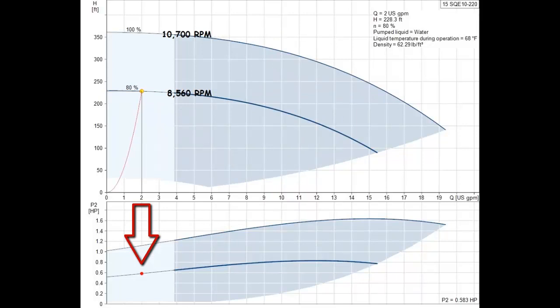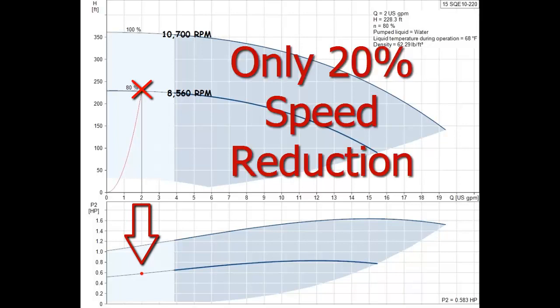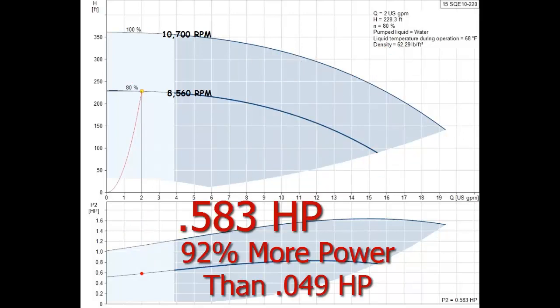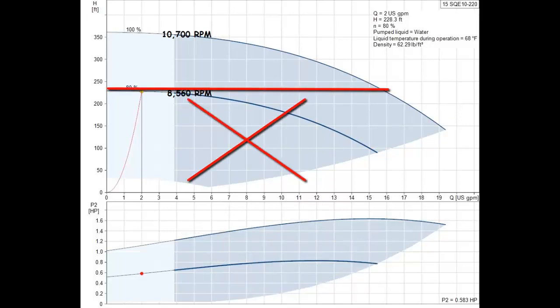As you can see, placing a point at 220 feet of head and 2 gallon per minute flow shows the pump can only be slowed by 20%. This requires 0.583 of a horsepower, which is 92% more energy than the 0.049 horsepower many would like for you to believe. The pump must always maintain 220 feet of head, so none of the shaded area below the red line is usable.